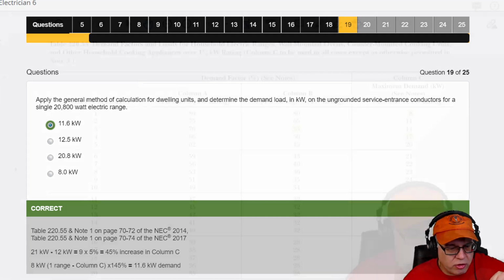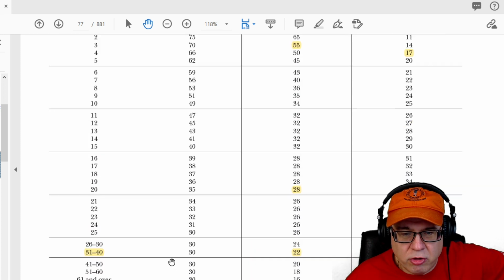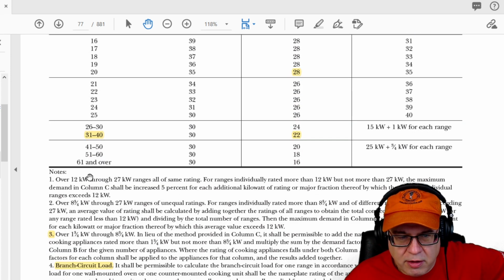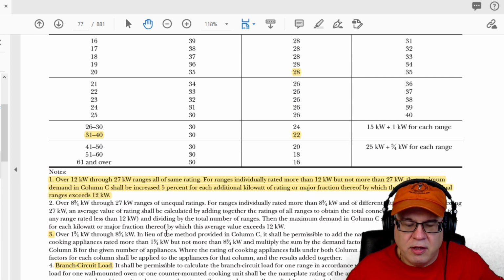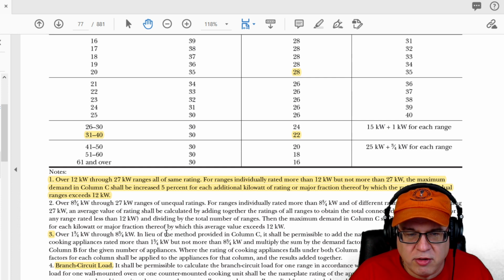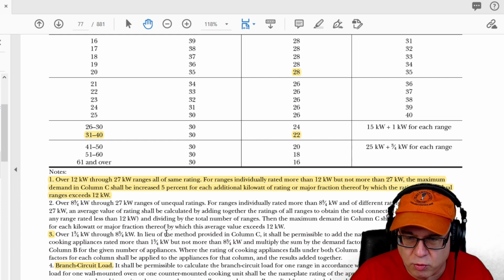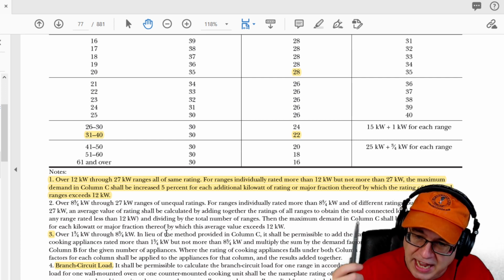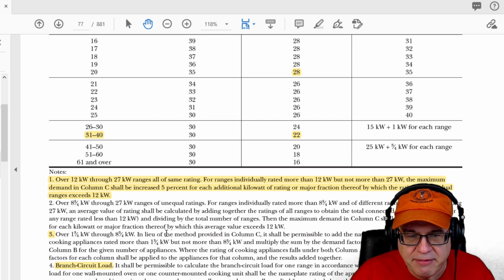Let's look back at the code just so y'all know. This is what Jay is using right here. Notice what it says, and I'll highlight it. It says, when it's over 12 through 27, ranges all of the same type. Okay, and we just have one, so it really doesn't matter, but it still applies. It says, for ranges individually rated more than 12, but not more than 27, the maximum demand in column C, and the maximum demand was 8 kW. That was the maximum demand for one range. Shall be increased by 5% for each additional kilowatt of rating or major fraction thereof by which the rating of individual exceeds 12.